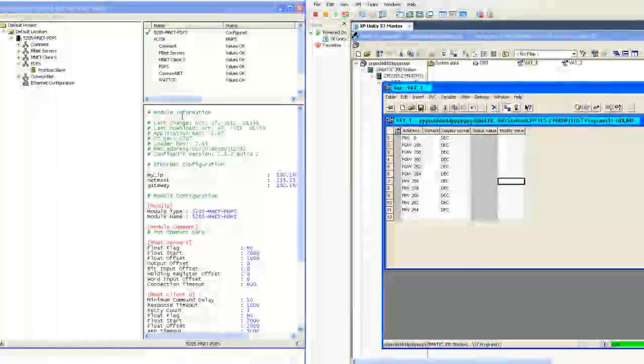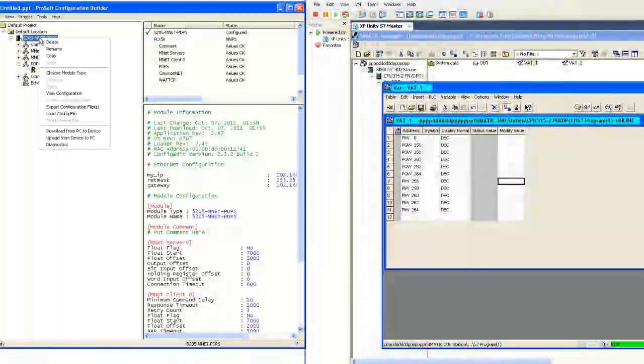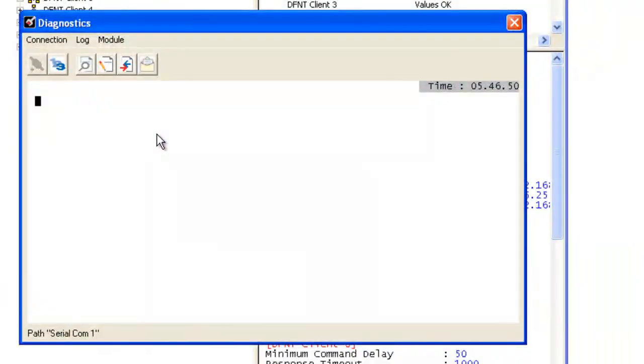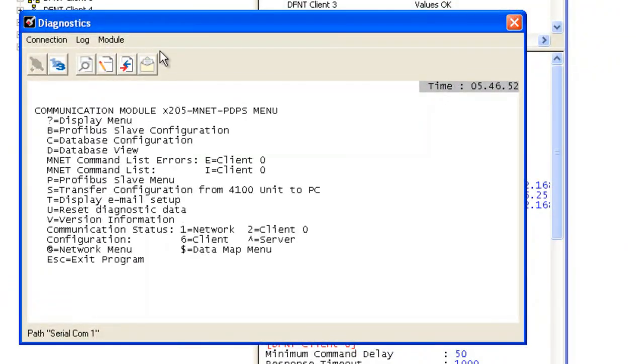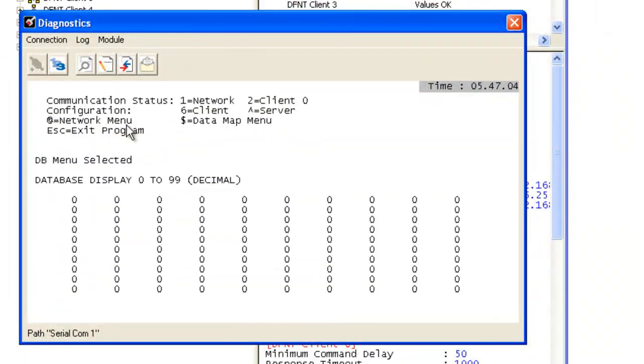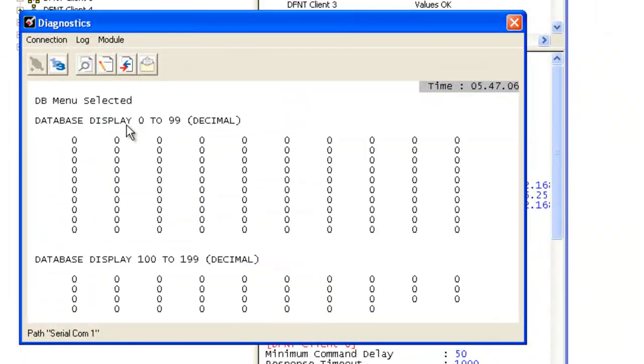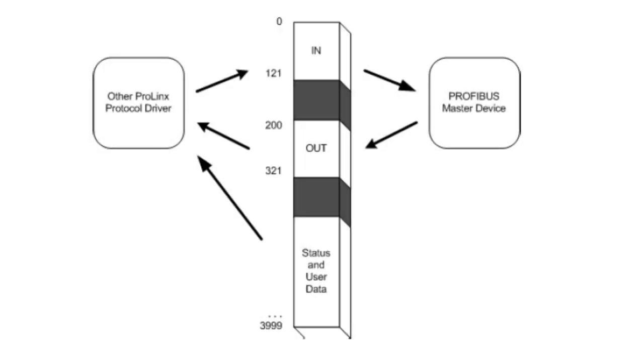Now we're going to show you how the data maps in. So we're going to right click on the module, select Diagnostics. Type question mark to get the menu. We'll type D for database view and we're going to type N for next and N for next to get to address 200, which is where the Profibus input is coming from the master. Here is a map of how the data is mapped in our ProLinx memory. Zero is going out to the Profibus master and 200 is coming back in with 121 words of data each way.